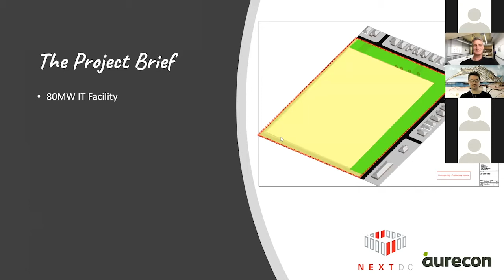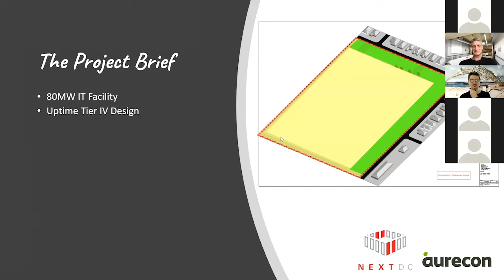So the project brief for the team was an 80 megawatt IT facility, translating to a 100 megawatt total facility load, with an uptime tier 4 design — basically a fault tolerant data center design, the top tier rating you can get.